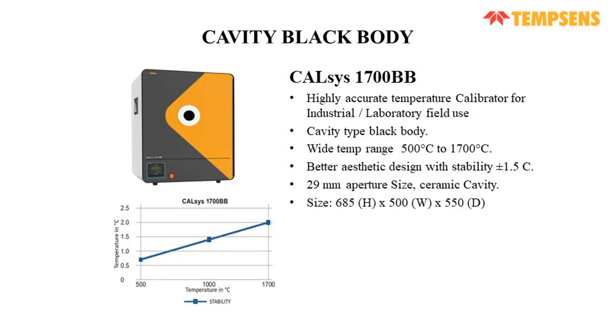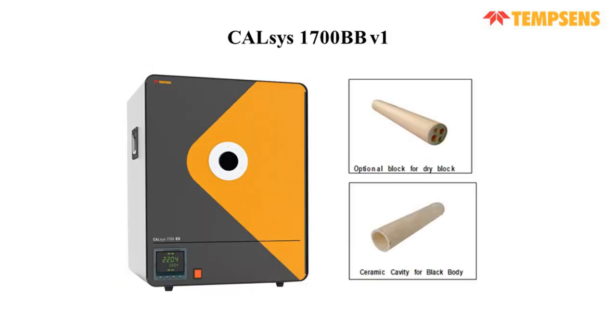Then the 1700 BB, and the temperature range for this is 500 degrees centigrade to 1700 degrees centigrade, with a stability of plus minus 1.5 degrees centigrade. The aperture size for this model is 29 and it has a ceramic cavity. So this is the cavity and block. The optional block for the dry block is a ceramic block and ceramic cavity. The block has holes to incorporate RTDs and thermocouples, and the cavity is for thermal imager and pyrometer calibration. These are inserted in the 1700 BB.